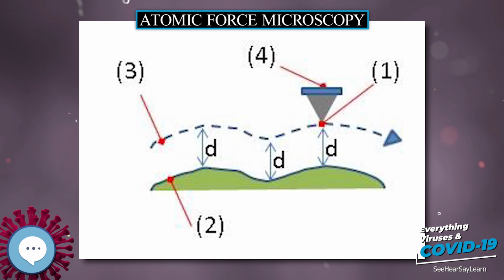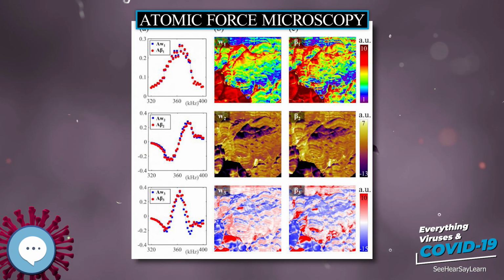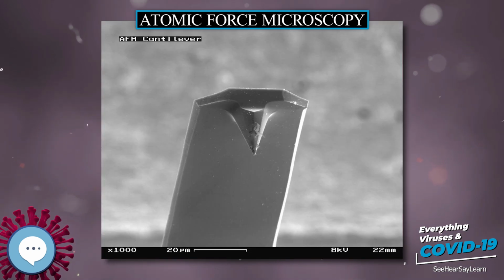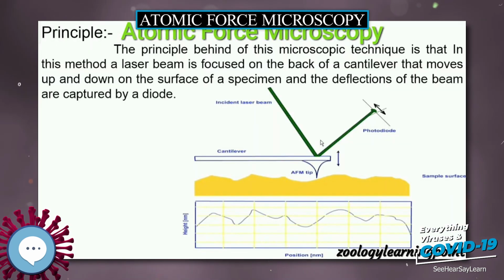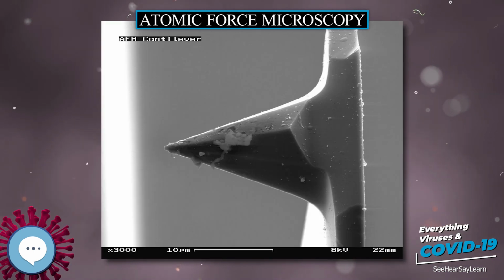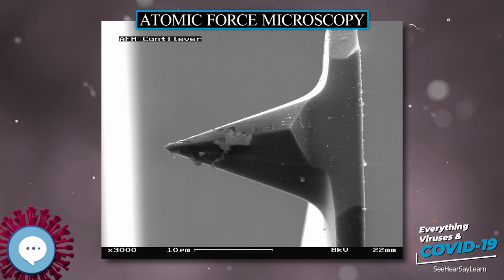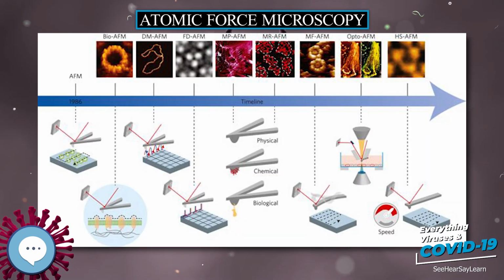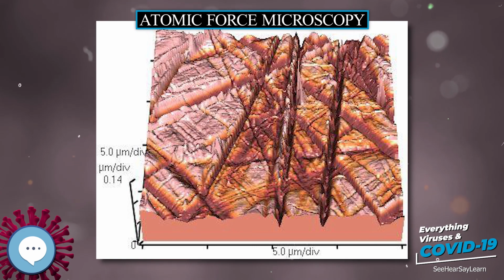The optical leverage, the output signal of the detector divided by the deflection of the cantilever, is inversely proportional to the numerical aperture of the beam focusing optics, as long as the focused laser spot is small enough to fall completely on the cantilever. It is also inversely proportional to the length of the cantilever. The relative popularity of the beam deflection method can be explained by its high sensitivity and simple operation, and by the fact that cantilevers do not require electrical contacts or other special treatments, and can therefore be fabricated relatively cheaply with sharp integrated tips.